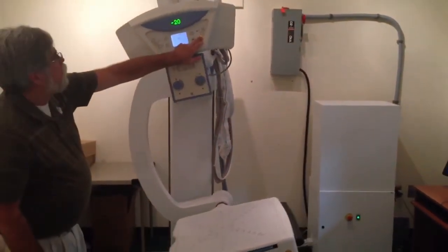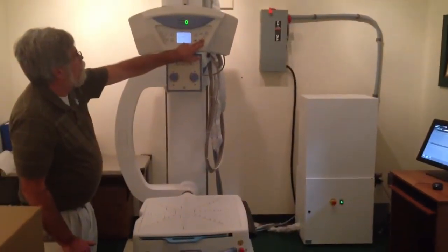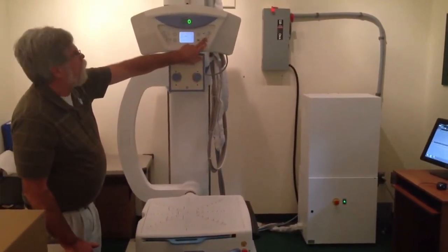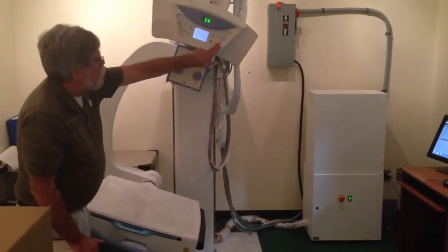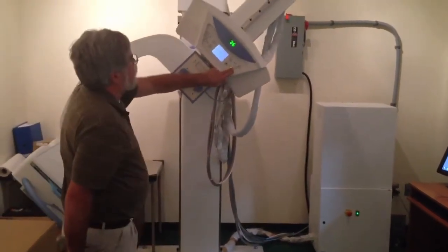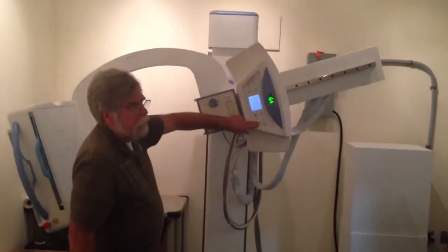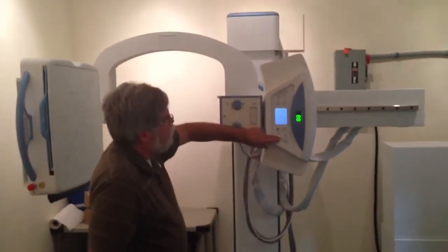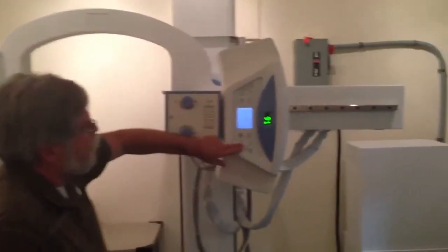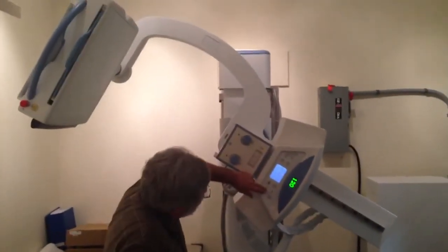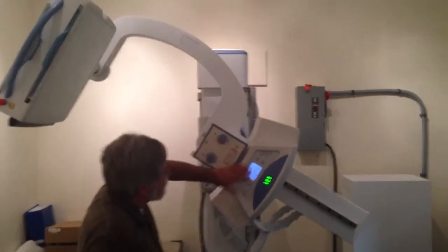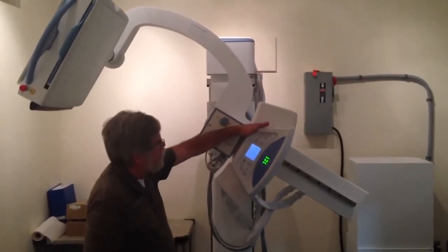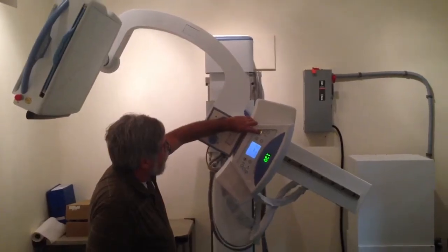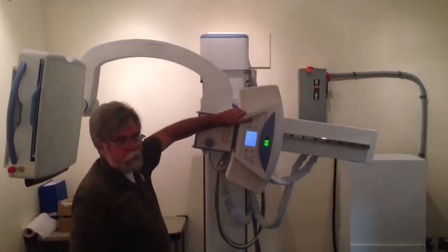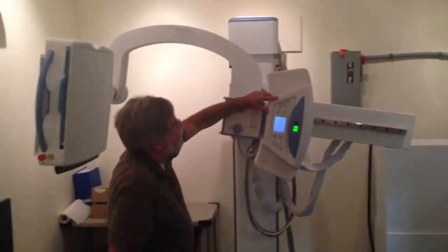I'll come back to vertical. It'll go to 0 degrees and then stop. If I want to continue on, I can continue to press the button. It will actually move out here, if it doesn't squeeze me, down to a 90-degree position and stop. And I have one more position I can get into with an automatic stop, and that is 120 from vertical. Okay? So those are the different positions that have automatic stops. Obviously, I can stop anywhere in between any of these motions to facilitate the particular type of exam I'm running.